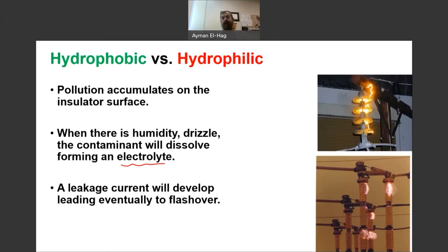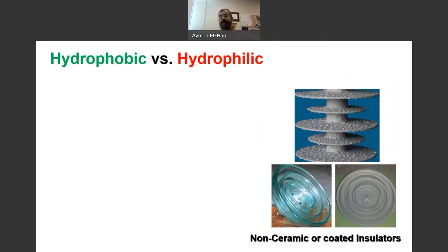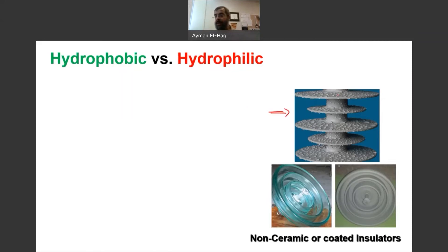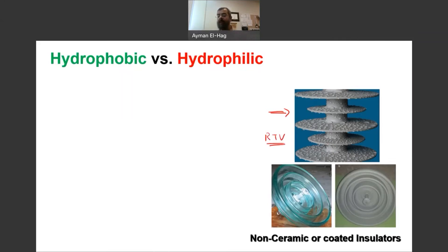So this is what we mean by hydrophilic. Now, what is hydrophobic? Hydrophobic occurs in the other class of insulators, which we call non-ceramic insulators, especially those made from silicone rubber. These insulators can come in two different forms: either as a full insulator, or as a coating — for example, a glass insulator coated with what we call room temperature vulcanized, or RTV, silicone rubber.